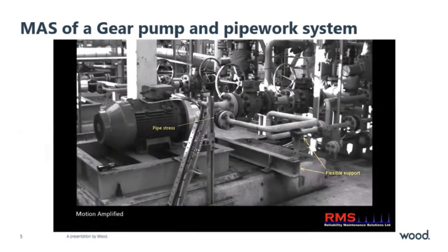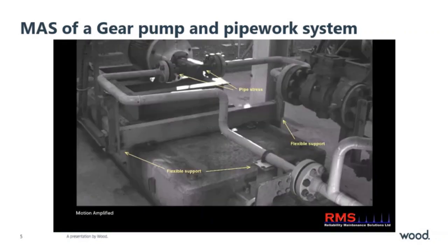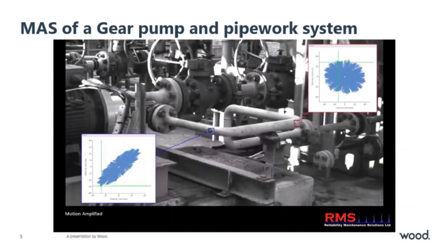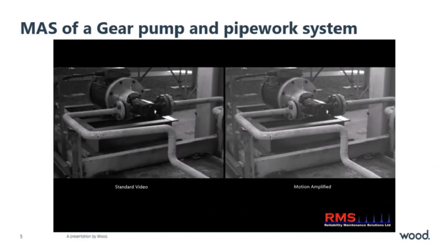The following video is a computer-generated amplified motion study. It uses a high-speed, high-resolution camera to capture the video. How it works is the software detects a repeating movement of the object colors, picking up frequency and displacement. Then by inputting a factor, say times 50 as we used in this video, it makes it look worse than it really is. So what's the point in having a fake video? Well, if you think of the movement as an accurate ratio between one object and another, that's why it's used.